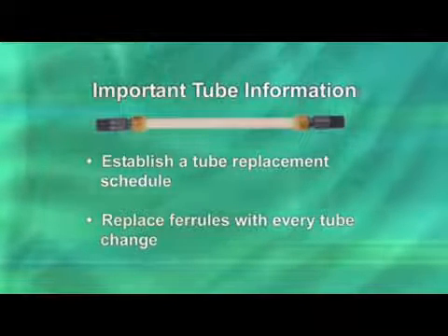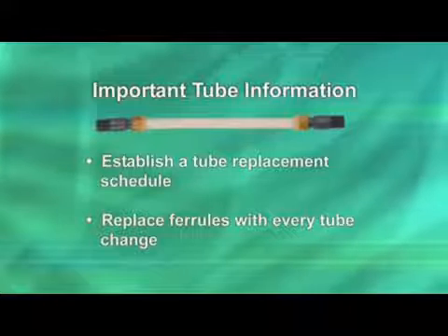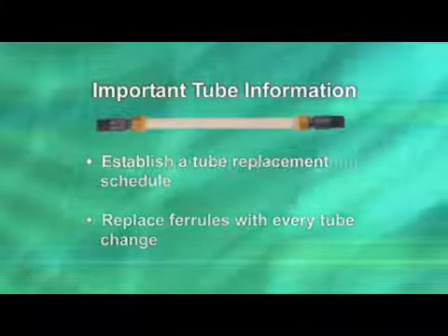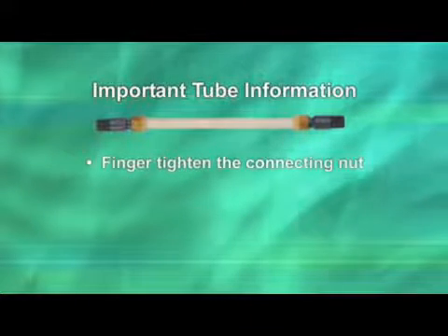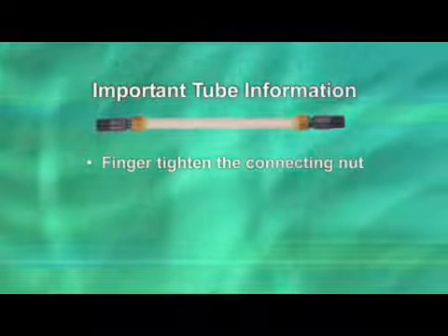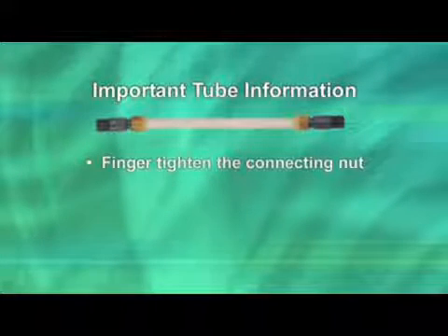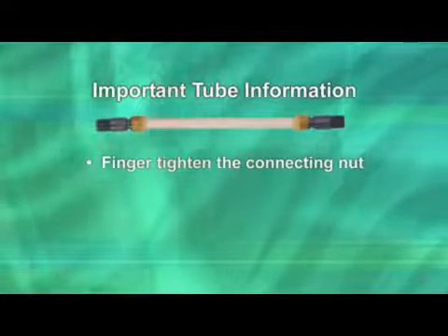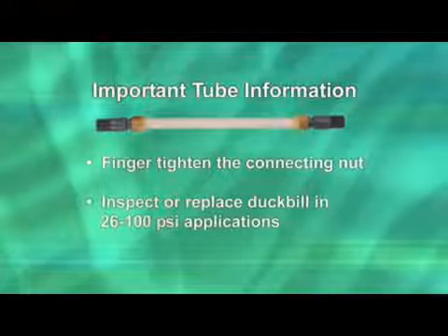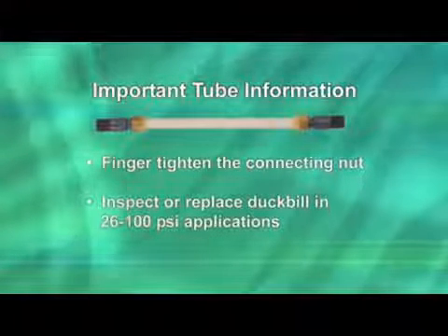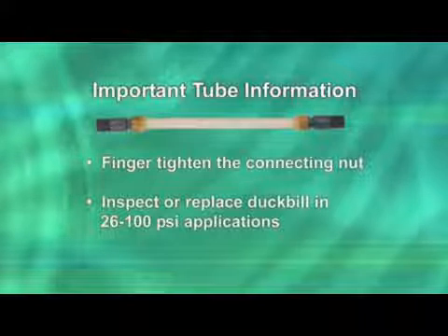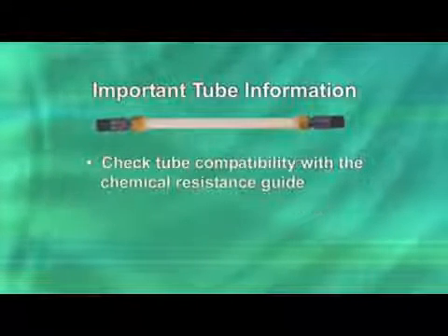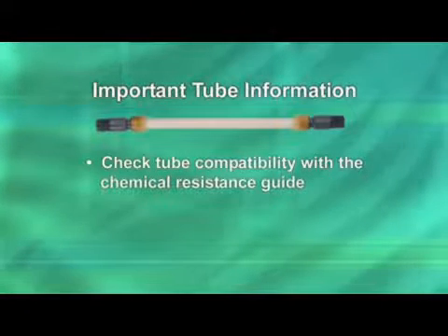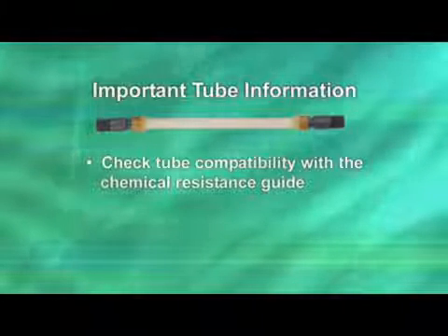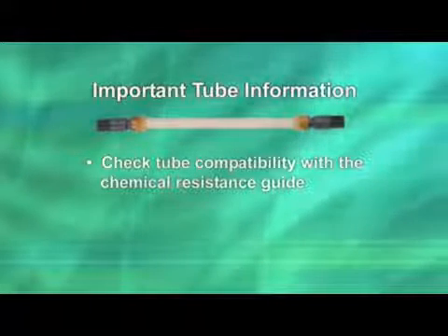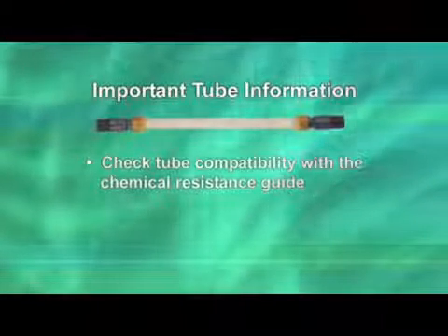The ferrules are the seat between the tube fitting and the connecting nut and are included with each new tube. Only finger tighten the connecting nut. Hold the tube fitting when tightening to prevent breaking the internal seal and the fitting from spinning inside the tube. For 26 to 100 psi applications, inspecting and replacing the duckbill at every tube change is recommended. Santoprene pump tubes are not compatible with petroleum or oil-based products. Refer to the chemical resistance chart in the catalog or on the website for compatibility, or call the factory.